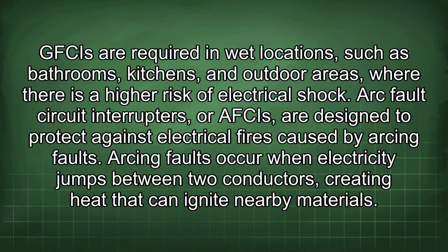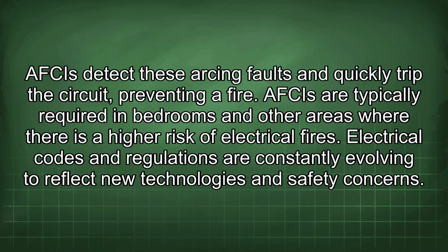electrical shock. Arc fault circuit interrupters, or AFCIs, are designed to protect against electrical fires caused by arcing faults. Arcing faults occur when electricity jumps between two conductors, creating heat that can ignite nearby materials. AFCIs detect these arcing faults and quickly trip the circuit, preventing a fire. AFCIs are typically required in bedrooms and other areas where there is a higher risk of electrical fires.